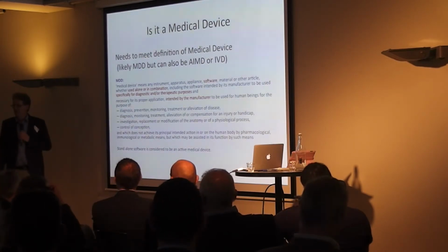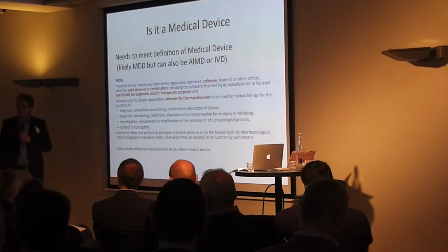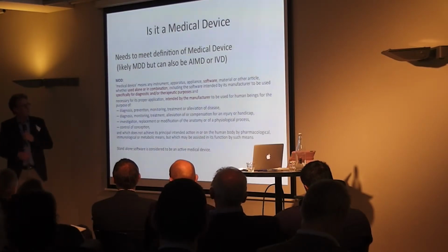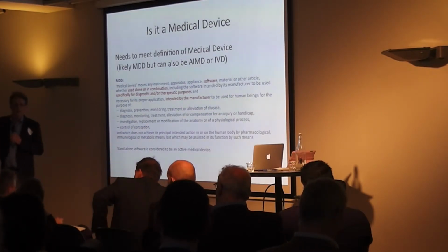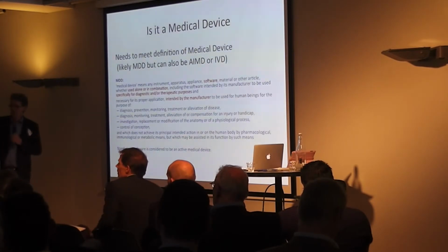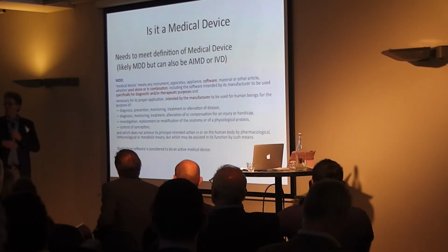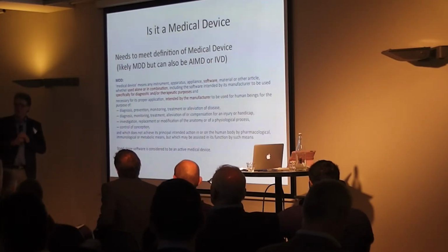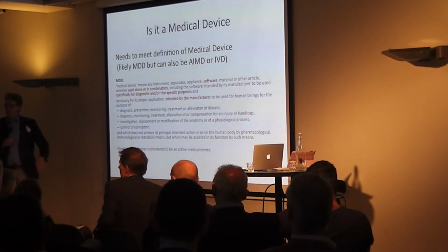But do you place it on the market, or do you keep it in your office and not market the product? That's the difference. You don't need to formally CE mark the product because you do not place it onto the European market. On the other hand, better be sure that it works as it should work. Exactly, because you're exposing yourself. Yeah, because the analysis that you do is based on this device. So you don't rigidly need to end up with a CE mark on your software because you don't place it onto the European market. Still, it needs to meet the criteria of correct analysis of the ECG.